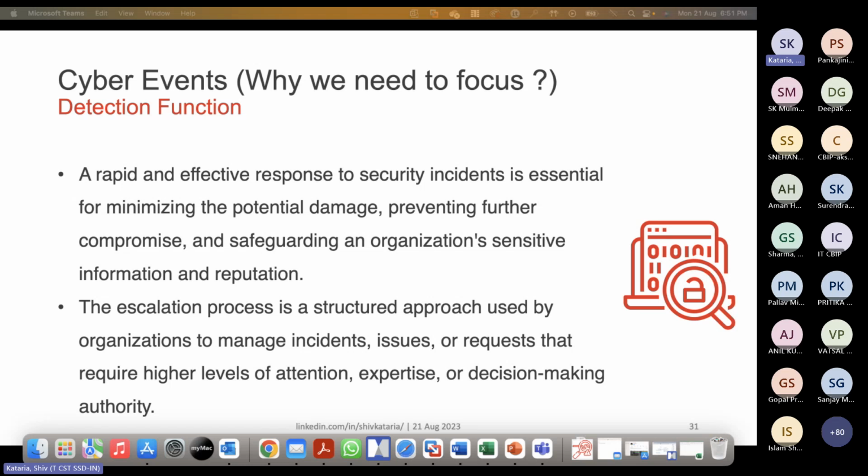And because of the malware, the system was trying to do some lateral infection. And due to that lateral infection, it would generate loads of traffic. The traffic will basically cause a denial of service on the network side, and the system will crash after this. So every time the crash happened, the people at the plant would basically restore the system again. But when we investigated the system, we identified, okay, it's not an issue of the OS or the hardware, it's basically the issue of the malware that is there.